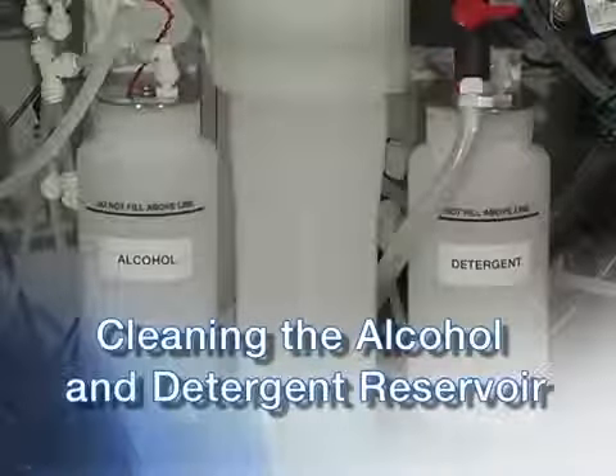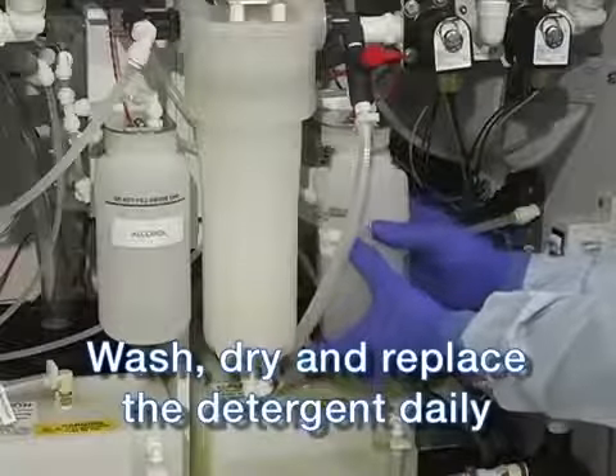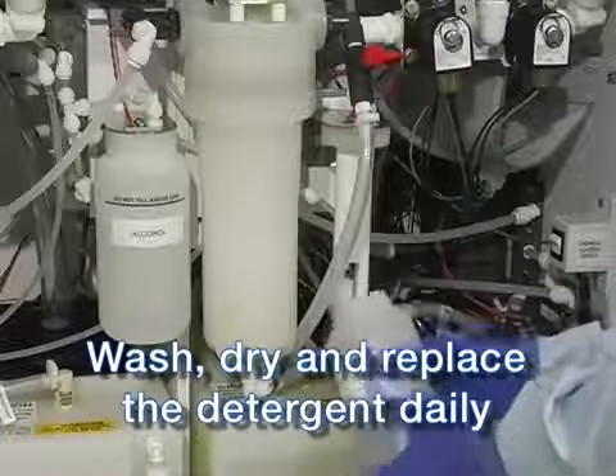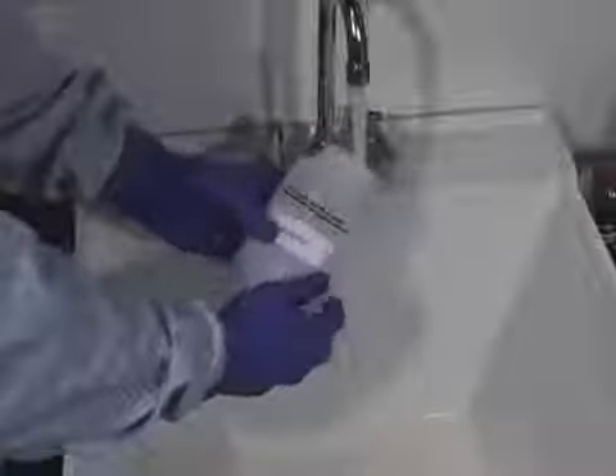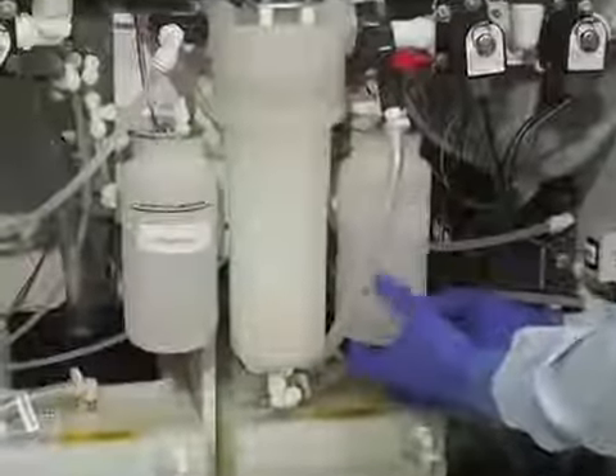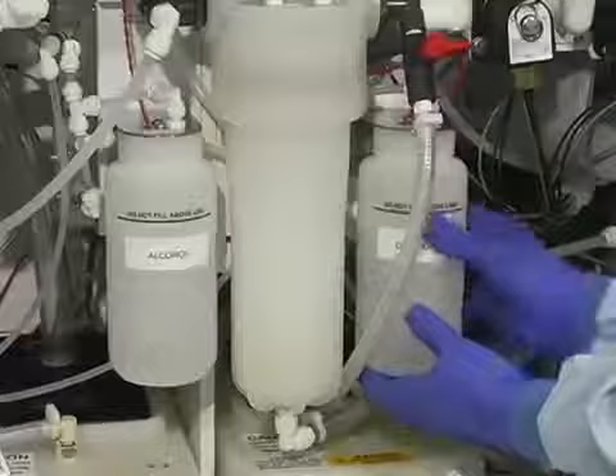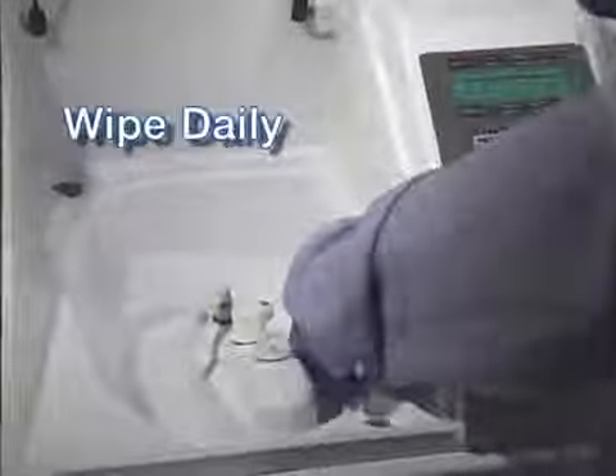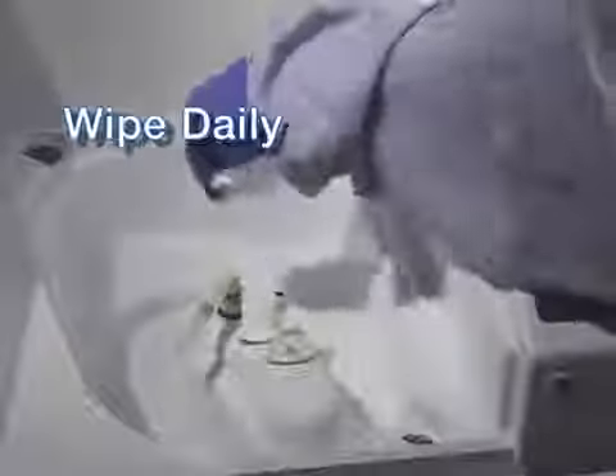The detergent reservoir should be cleaned daily. Detach the reservoir by unscrewing it from the fixed cap. Make sure the reservoir is rinsed with hot water to remove all detergent residue. Dry the detergent reservoir completely. Then screw it back onto the fixed cap on the right side of the internal water filter housing. Sanitize the handles of the cover and floating lids along with the exterior of the DSD at the end of each day with a damp, lint-free cloth wetted with an EPA-registered sanitizer.